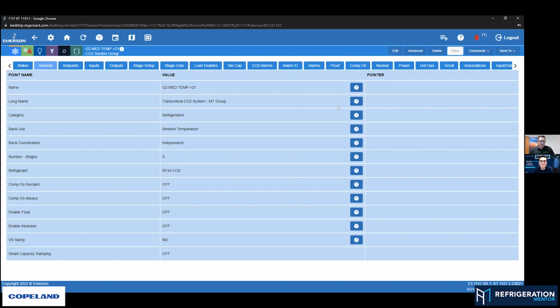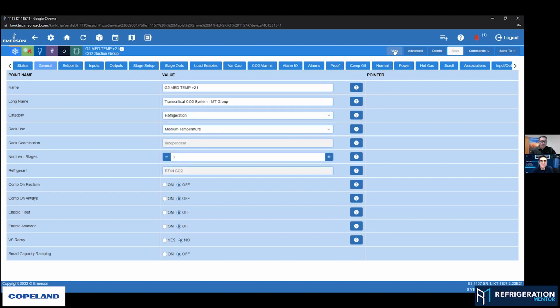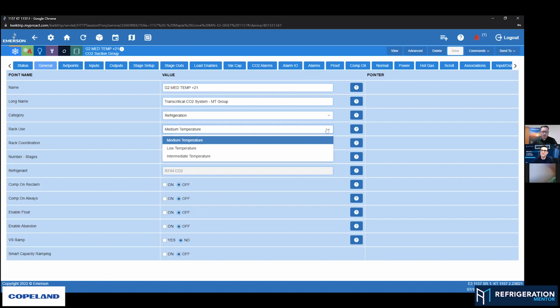As far as setting up the CO2 suction group in the E3, you come through and tell it what kind of suction temperature application it is. You have the option to do medium temperature rack, low temperature, or intermediate temperature, which is sometimes also called parallel - the three different types of suction groups we see in a CO2 transcritical system. This makes it very easy to differentiate between those, and there are a few parameters that will cascade in other tabs depending on what you select here.